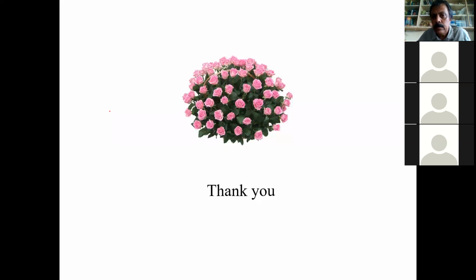Yeah, next question, Varun. Does pump impeller material have impact on efficiency, like SS, bronze, etc.? No, whether it is a bronze impeller or a stainless steel or cast iron impeller, it all depends on the liquid that the pump is going to handle. So nobody chooses the material of the pump for the sake of efficiency, and it does not have a big impact on the efficiency. It's basically the profile of the impeller which determines the efficiency.